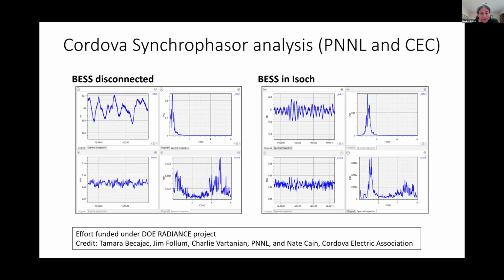This is initial. They're still working on tuning, but they were able to use the micro PMU and come up with a frequency spectrum of what the oscillations look like. And what it seems is that at this point there may be a 1 to 2 hertz power oscillation that is introduced when the BESS is in isoch and the hydro is also regulating frequency.